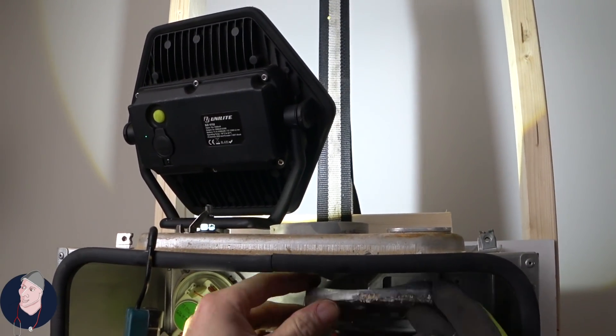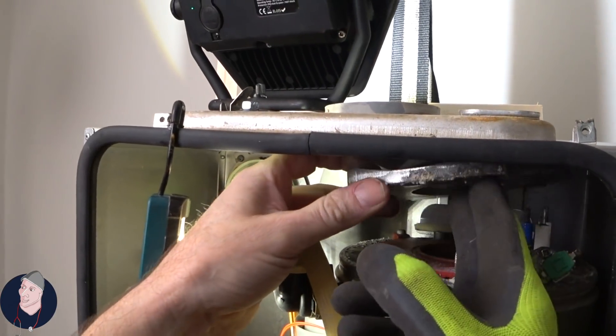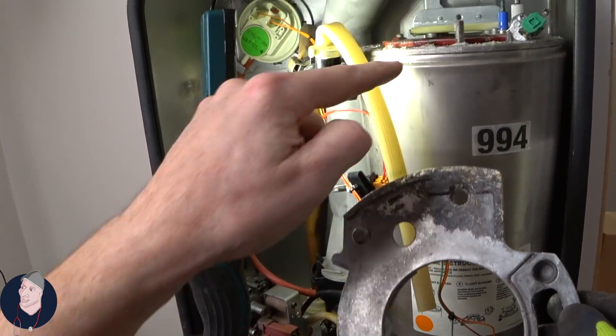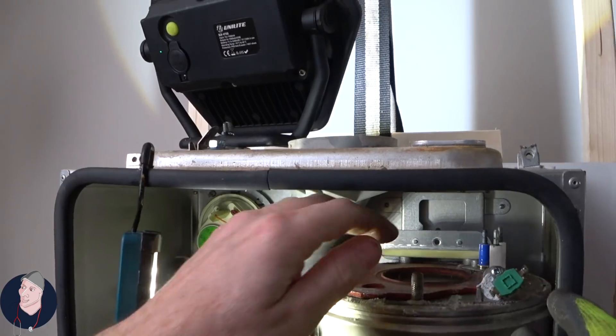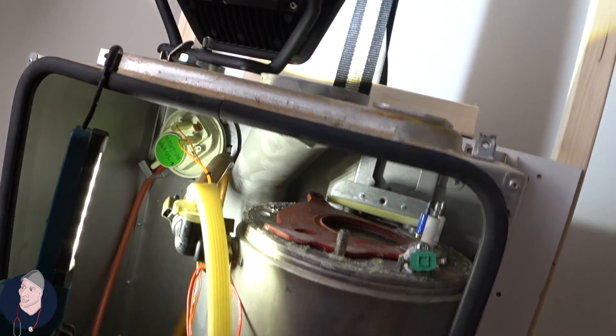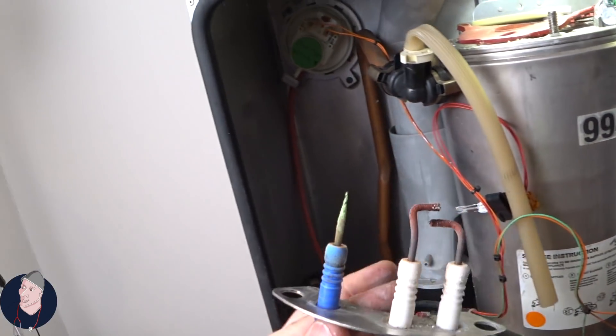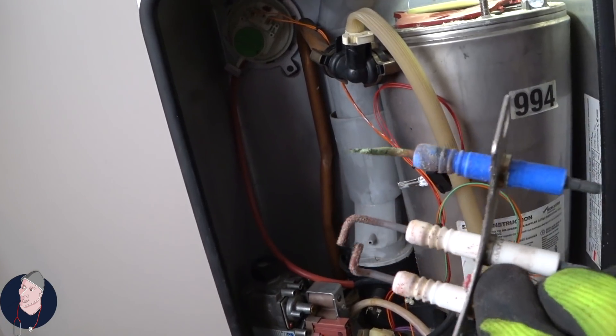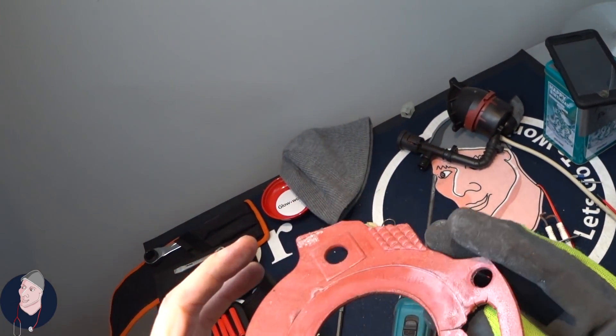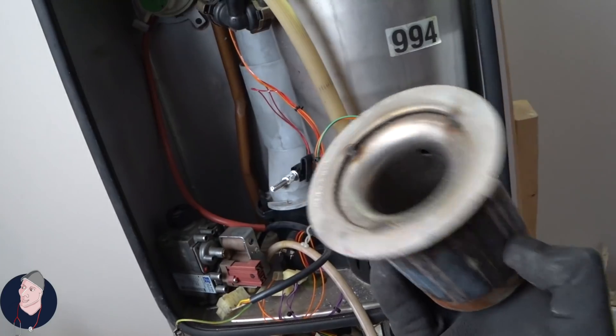Lift up, lift out. Clearly you can see here there's been some issues. If we grab a hold of the electrodes — this is the access for when you have to clean the baffle. I'm just going to take the two out. Clearly that's never been serviced.